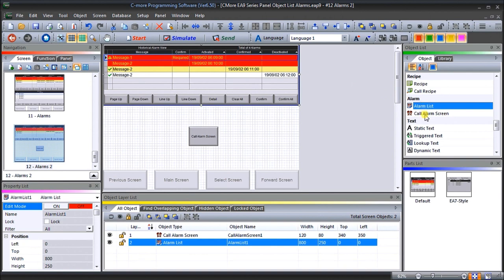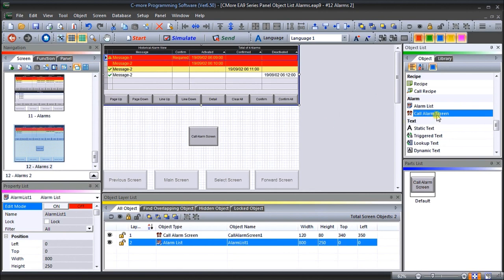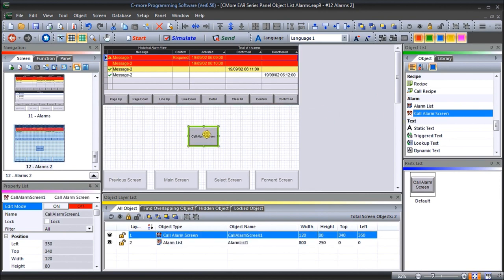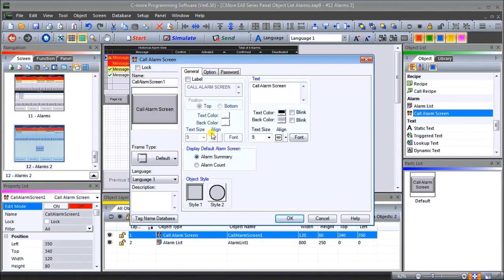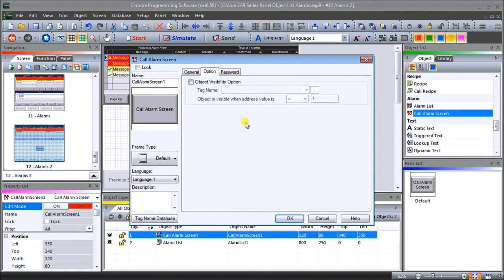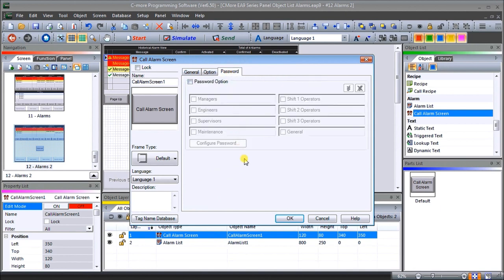We also have our 'call alarm screen', which is actually a button we drag over. When we click on it, we see we have our alarm call screen — this will call up a pre-programmed screen in our system that will display alarms. We set the color, we can have alarm summary or alarm count — we'll leave it at alarm summary. Under 'option' we have our visibility, and in this particular case we can actually put passwords in so that a password is needed in order to see those alarms, confirm them, or acknowledge them.